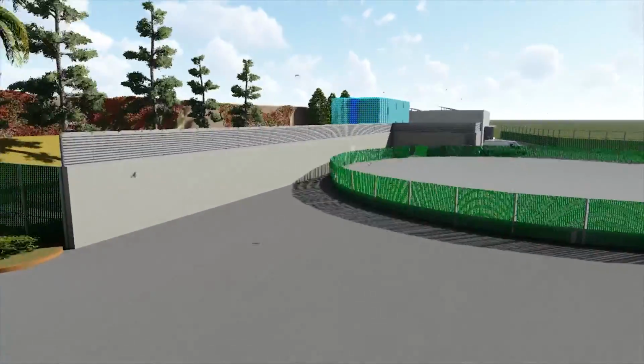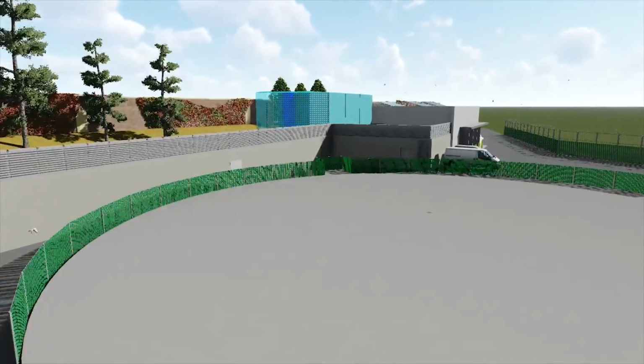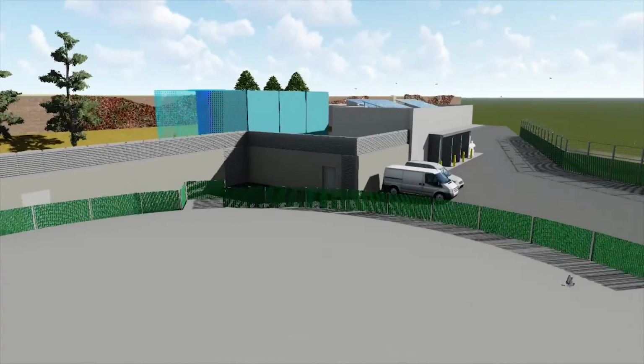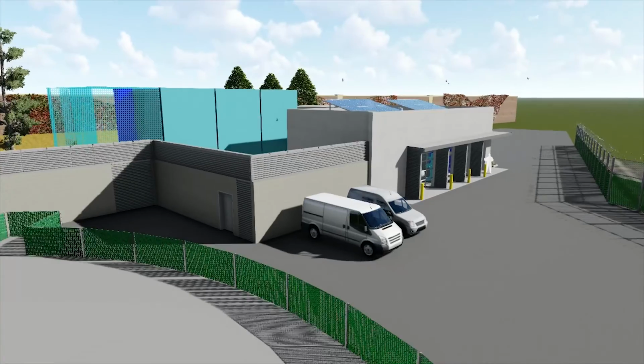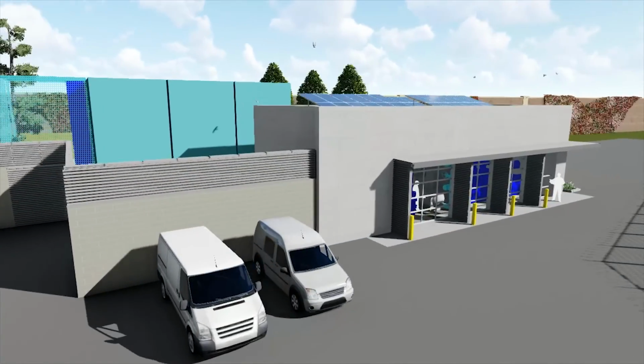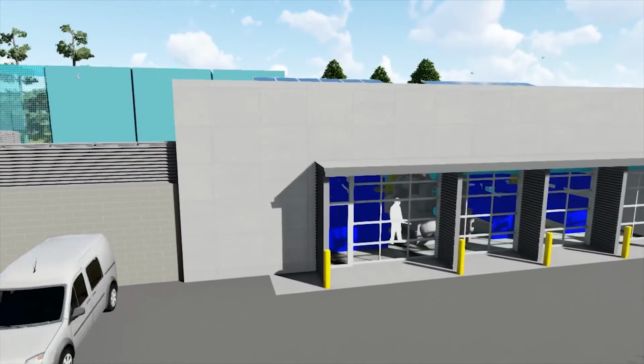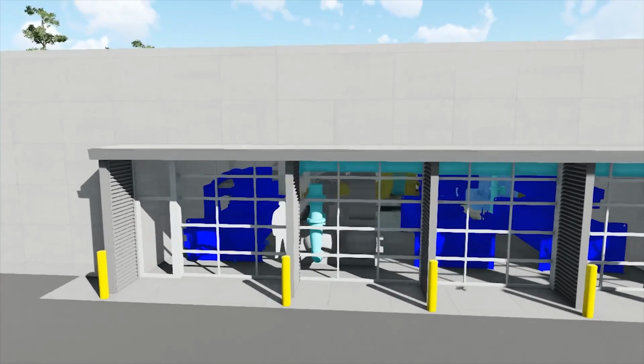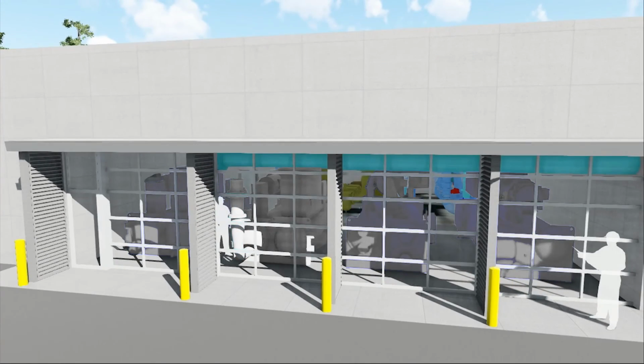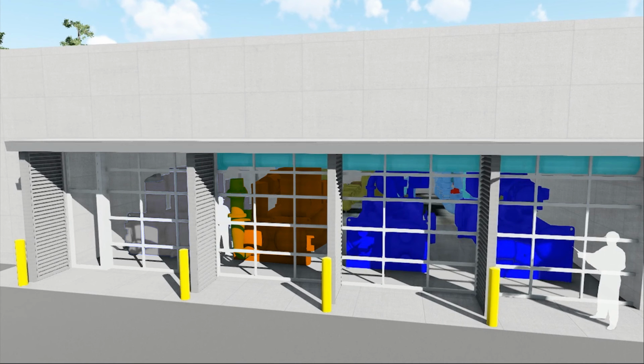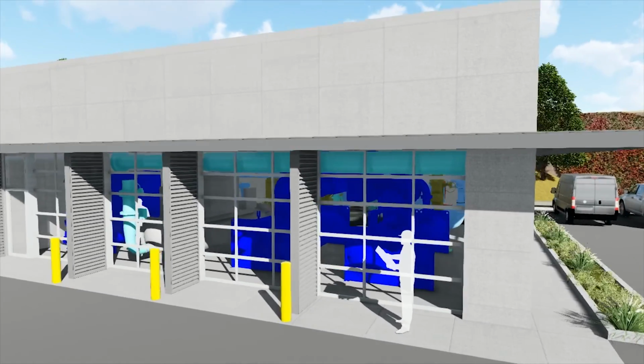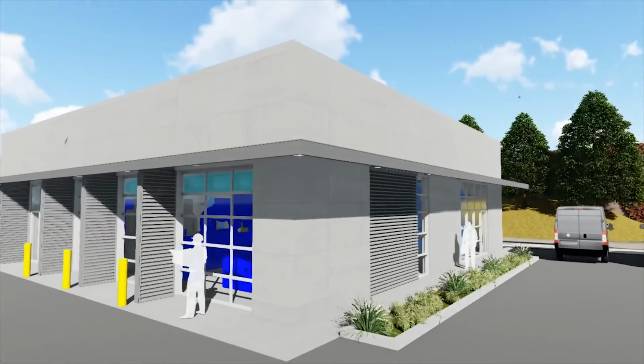The first element of our proposed project is the provision of a new central plant on the southeast side of the campus. A new sustainable building incorporating natural daylight and easy-to-maintain building materials will be constructed and sized to accommodate 4 1,000-ton chillers and associated chilled water and condenser water pumps. The plant will include a new 1,000-ton chiller and 2 existing 1,000-ton chillers relocated from the existing modular chiller plant. The relocation of the chillers will be in compliance with OSHPD published PIN 55.